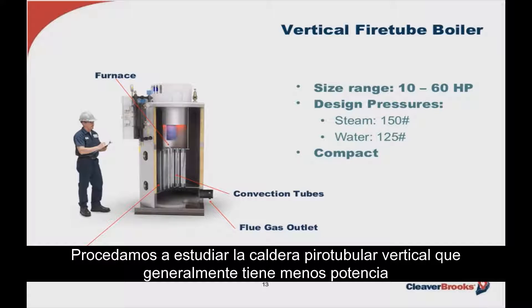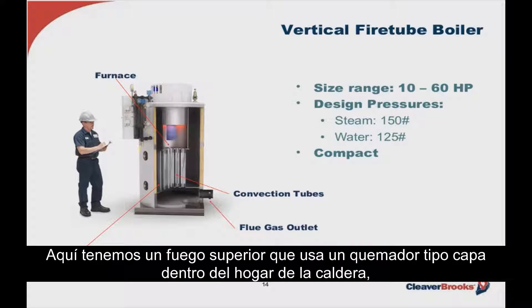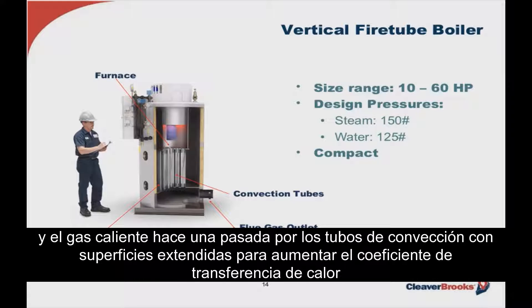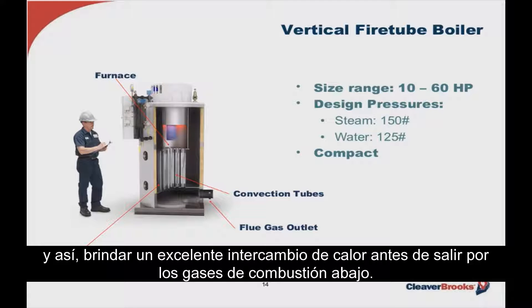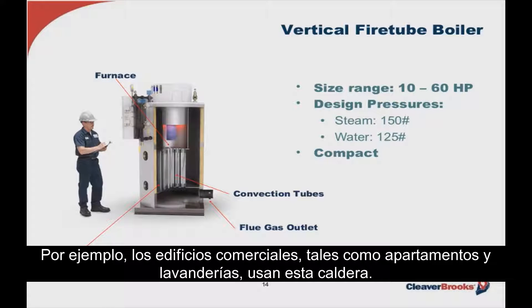The vertical fire tube boiler typically has a smaller horsepower range and fires either from the top down or with the burner mounted on the side at the bottom. This picture shows a top fire using a mantle-type burner firing into the furnace, with the hot gases making one pass through the convection tubes using extended surfaces to greatly enhance the heat transfer coefficient, affording excellent heat exchange before exiting through the flue gas outlet at the bottom. These boilers are used in commercial and industrial applications especially where space is an issue, such as apartments and laundries.